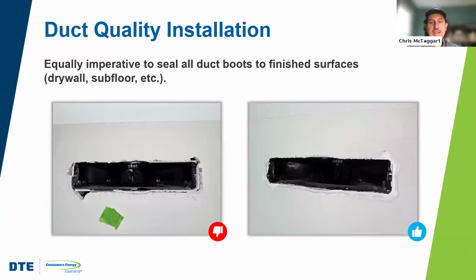Okay, so moving on. Again, the boot to finish surface connection, very critical. So we see two photos here. The one on the left shows a pretty typical install if you were to remove a grill and to take a look at how the boot, which is the rectangular typically, fitting that then connects to the finished surface, whether it's a wall or a ceiling or a floor. The boot to drywall connection needs to be nice and clean and tight.